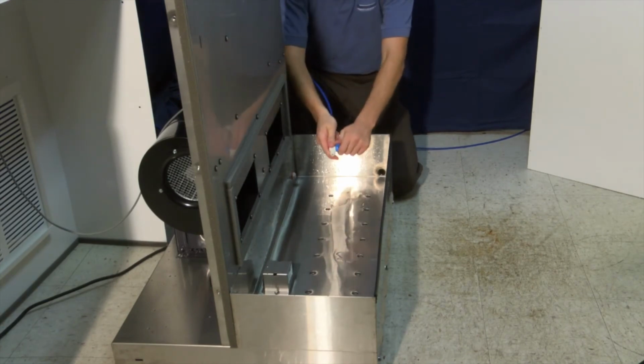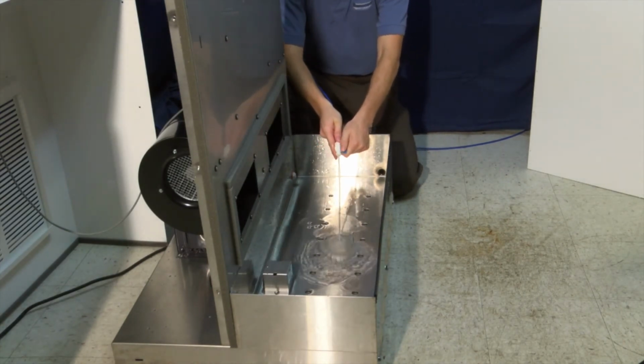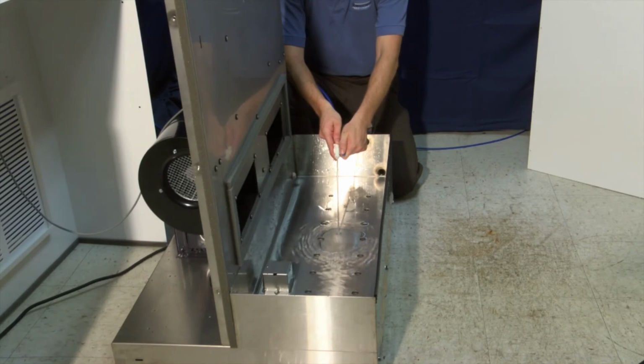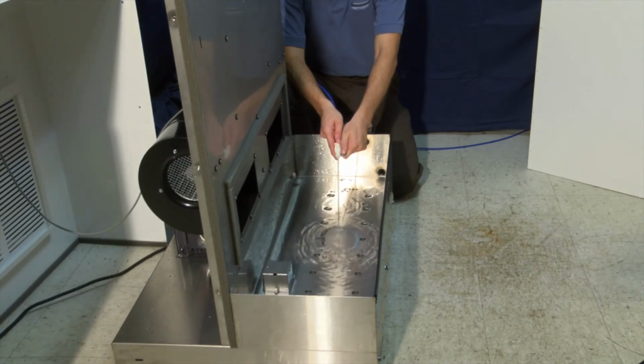After cleaning the unit, prime the transducers with about 1 inch of water, just like at startup. You can think of the water pan like an aquarium. If you clean it regularly, it will be fast and easy to manage. If you wait until it is a murky, dirty mess, it will be that much harder to fully clean, and damage may already be done.